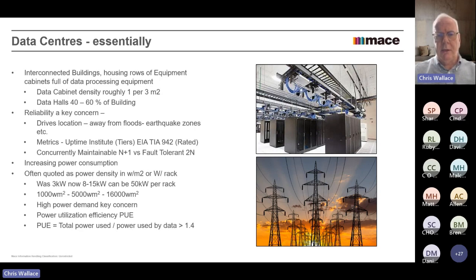The other big issue about data centers, and this is probably at the heart of why they've become a little bit controversial, shall we say, is the increasing power consumption. The power consumption is often quoted as a power density, either in watts per square meter or watts per rack. It used to be about 3 kilowatts a rack. That was not a bad density that you would see. Now, 8 to 15 kilowatts per rack is common. It's not that unusual to see up to 50 kilowatts per rack. So in terms of watts per square meter, it used to be about 1,000 watts a square meter. It can be 5,000 or even 16,000 watts per square meter. You have huge, huge power loads on these data centers.